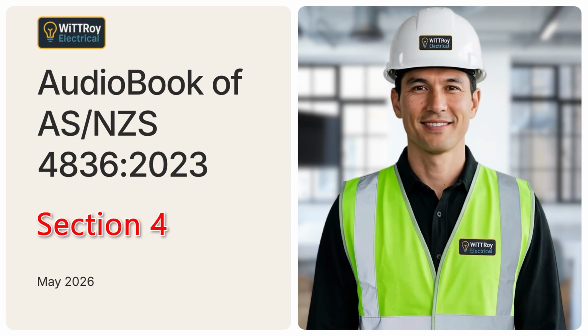Clause 4.3.8. Electrical equipment producing high voltages, HV. Clause 4.3.8 explains electrical equipment that can produce high voltages. High voltage, or HV, means voltage higher than low voltage. Some equipment can produce high voltage even where the supply arrangement may not appear unusual. Examples include cold cathode lighting systems, outline lighting systems, X-ray equipment, and open-circuited secondary terminals of current transformers. Some of this equipment can have open circuit voltages up to 15,000 volts.